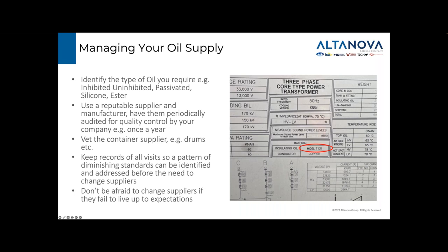The O in O-NAN is for oil, whilst K refers to the fire class of the liquid being greater than 300 degrees C, which is superior to that of mineral oil. The N refers to where the fans and pumps are, whether they're present or not, and this changes to F where they're present. The A is for the type of external cooling medium, e.g. A is for air, but this could be W for water, for instance.